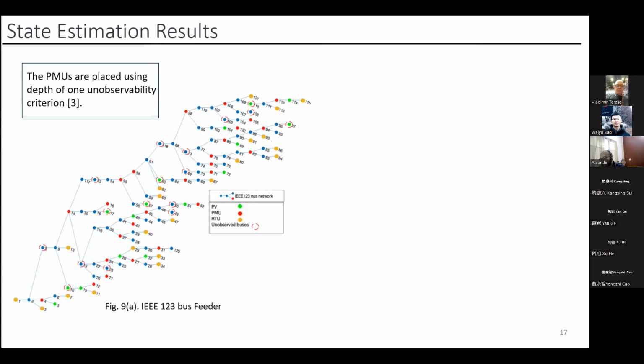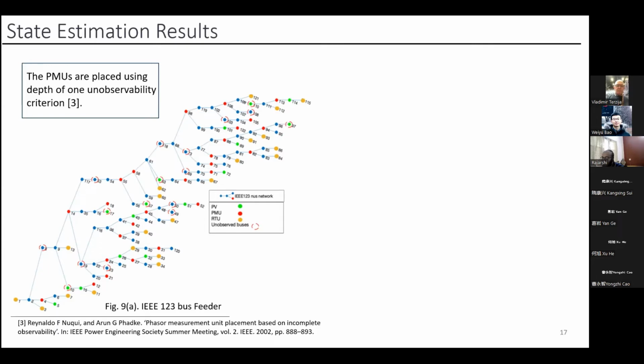The PMUs in this network are placed such that we achieve a minimum number of PMUs while meeting a criteria called depth of one unobservability. This ensures every unobservable node has its neighboring node as observable, so there are no two consecutive unobservable nodes in the system. The idea is that we try to gather information for an unobservable node from its neighbor, so we want that neighbor to be at least observable, and we achieve this using the depth of one unobservability placement criteria for PMUs.